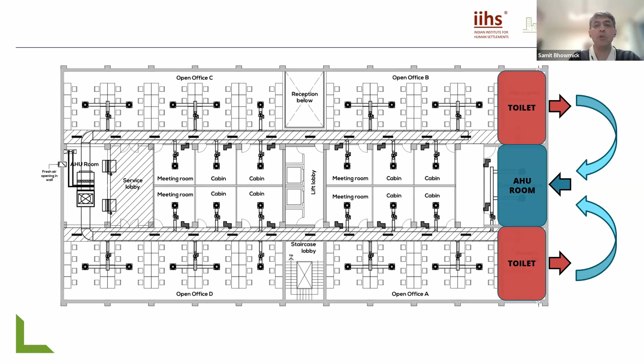I hope everyone's aware of what the AHU room is. This is a room with an air handling unit that draws in outside air, takes back return air from the space, mixes it up, cools it, and distributes the air back into the space. We need outdoor air to remove pollutants, carbon dioxide, and other things we exhale, to maintain a certain indoor air quality. If you have the toilets and AHU rooms on the same side, there's a very high risk that objective won't be achieved.